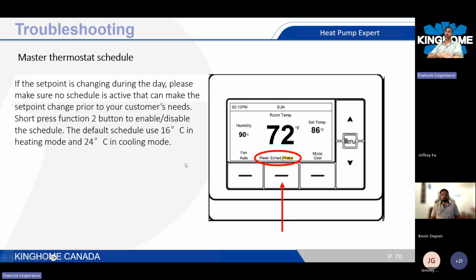Okay. So basically, the default schedule set point is 16 degrees in heating mode and 24 degrees in cooling mode. So during the off period, whenever it's at night or stuff like that. When the customer plays with the temperature, the system will catch it up, but at the end of that period, it goes back to 16. So it was cold inside the house at that point.